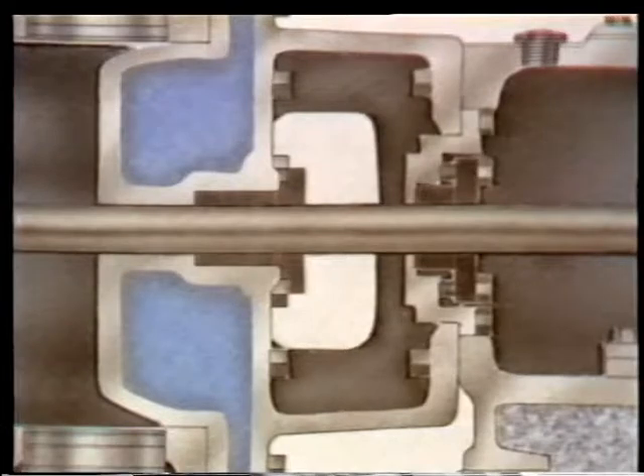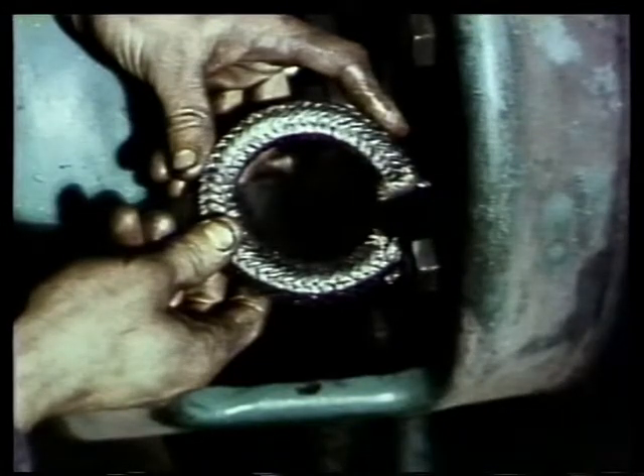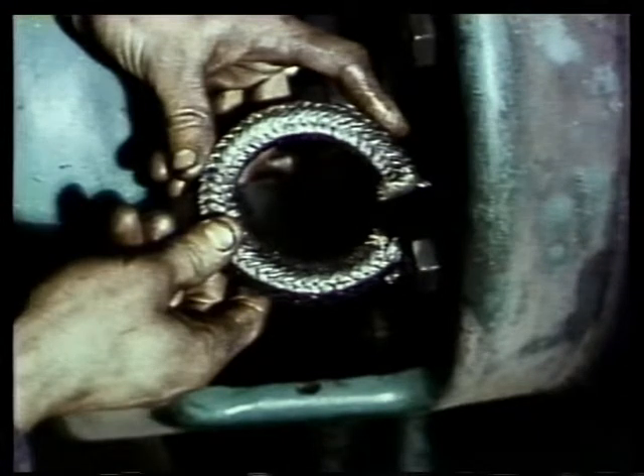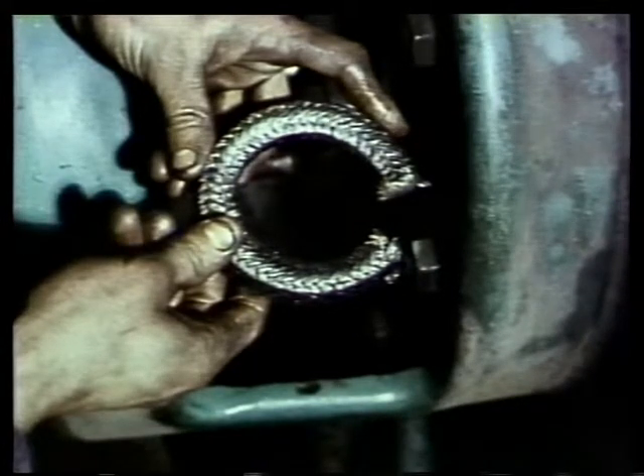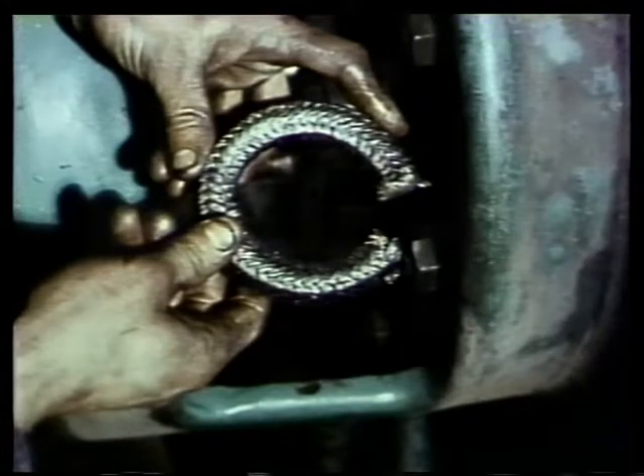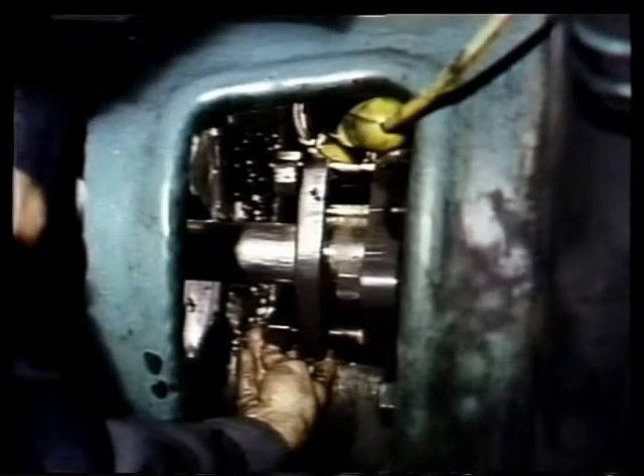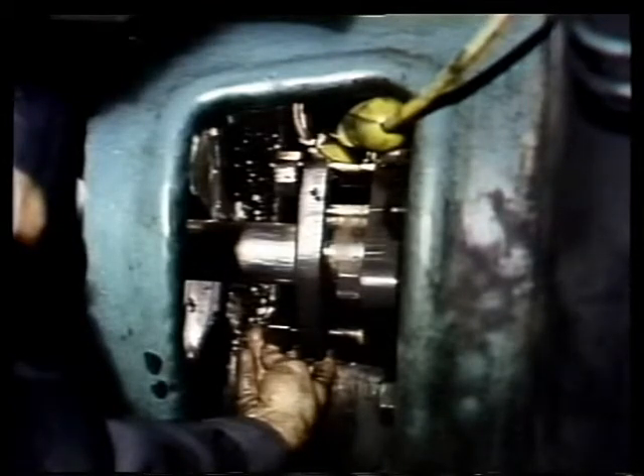The next step is to place the new packing in the stuffing box. The packing is a special kind that is made just for reciprocating air compressors. Always check the manufacturer's manual to be sure you're using the right kind of packing. After the packing is in the stuffing box, tighten the gland follower just enough to hold the packing in place. This is just a preliminary adjustment, which will be completed later.